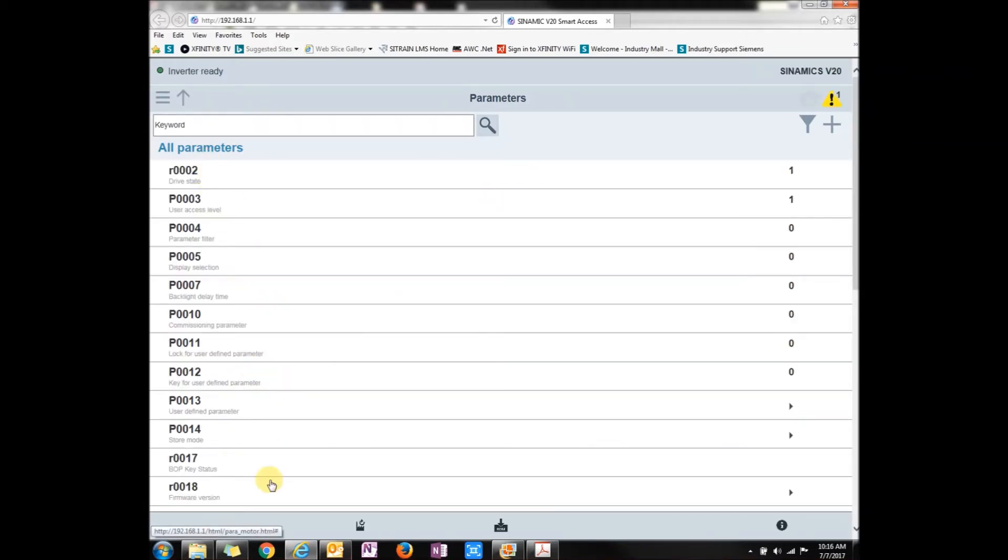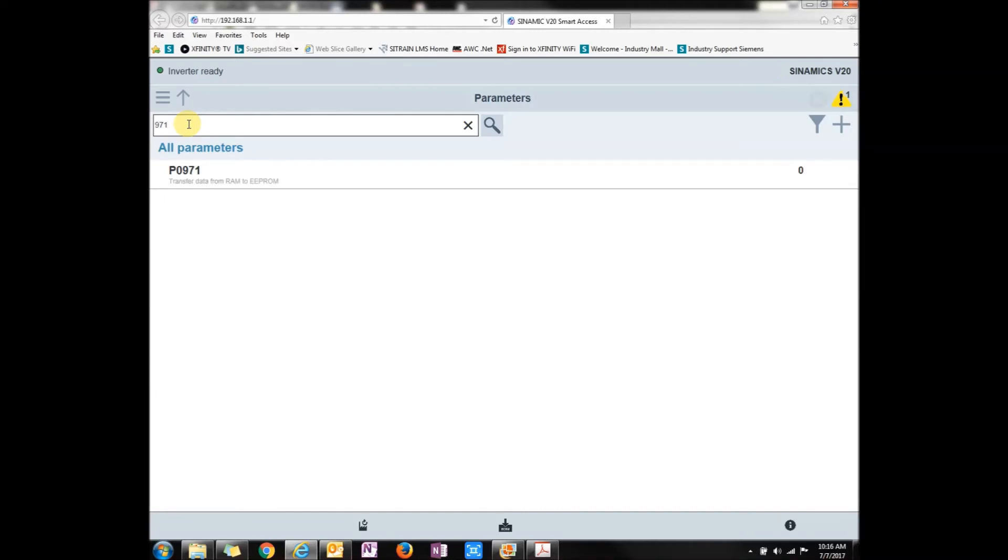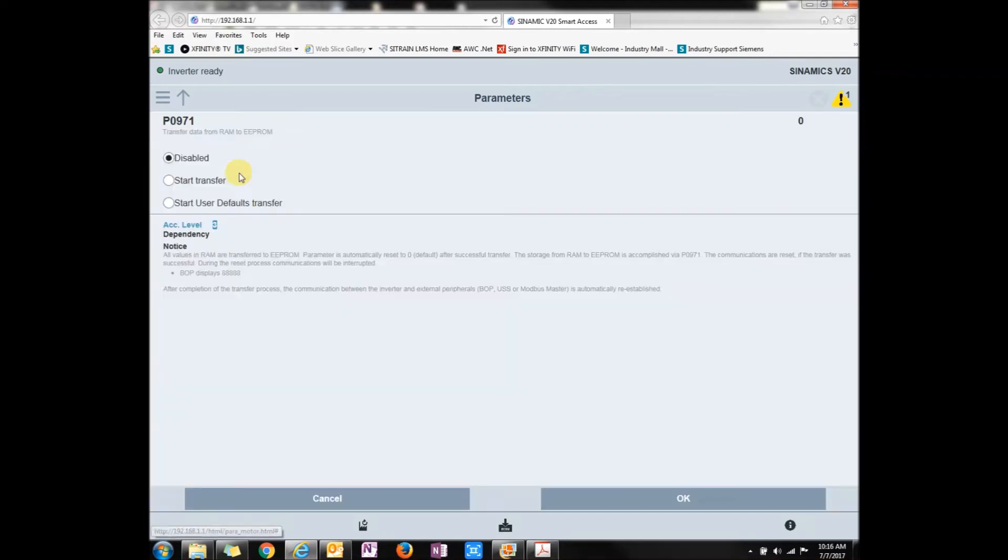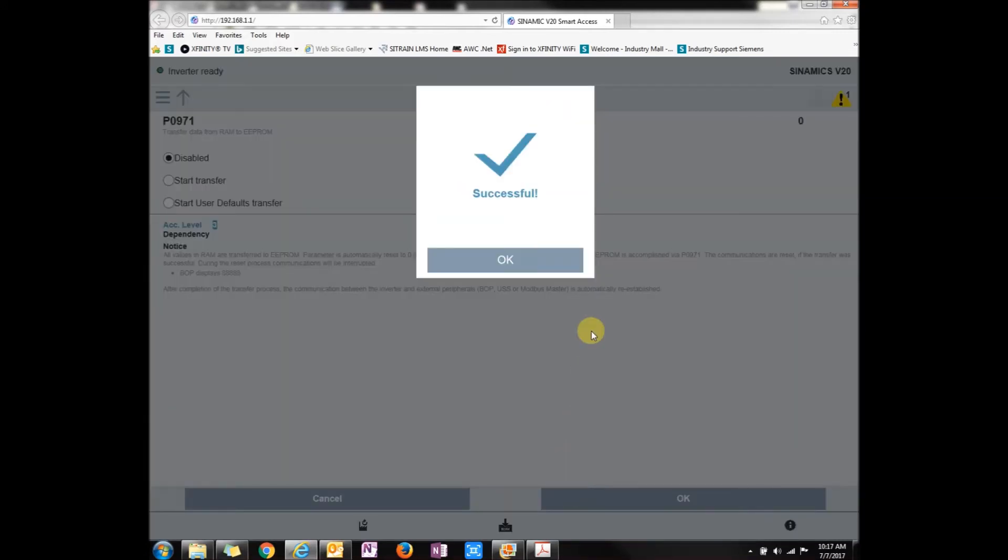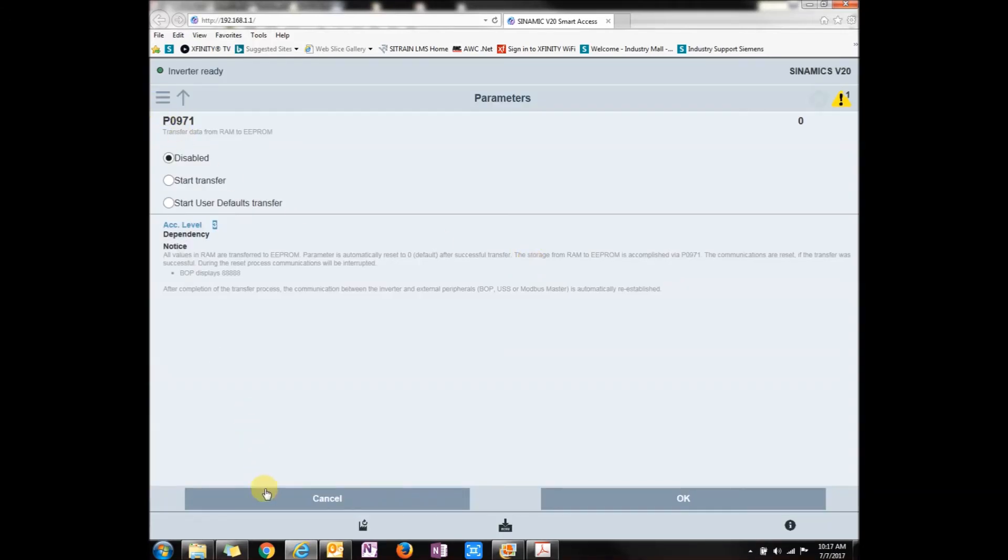Another thing that you can do is go to parameters. Here's the whole list of parameters that you can look at. One good thing is you can type in keywords, like 971. That would be something that I use all the time, which is save RAM to ROM. So I just typed in 971, it found it right away. Also, when you click on the parameter itself, it shows you what it can do: start transfer, user transfer. It describes everything for you, so you don't have to really pick up a manual. Let's press OK. Successful.